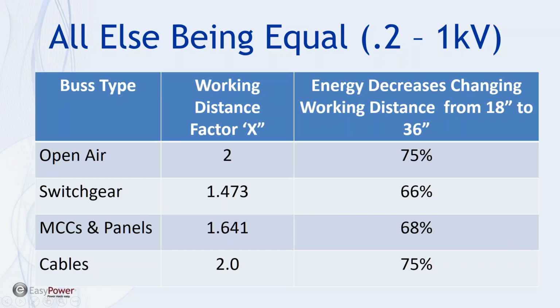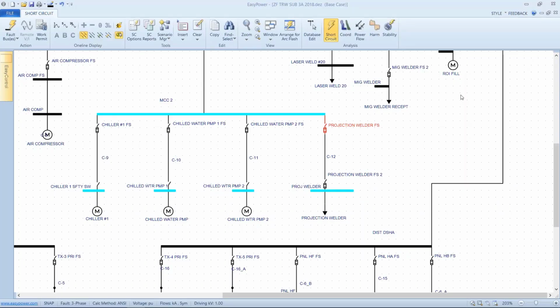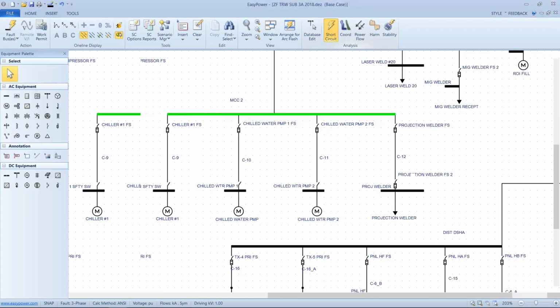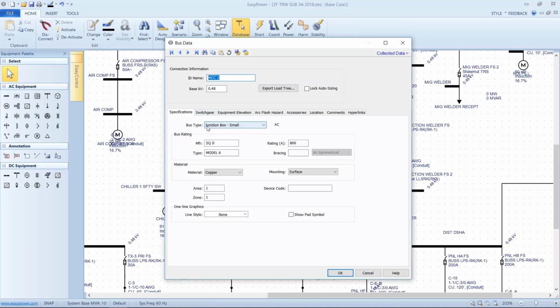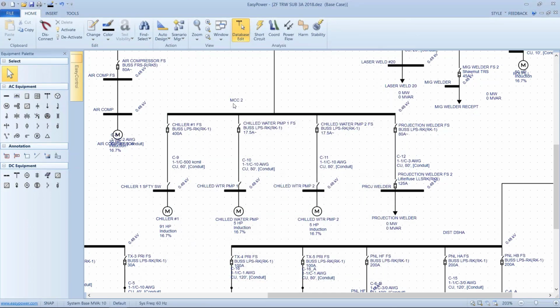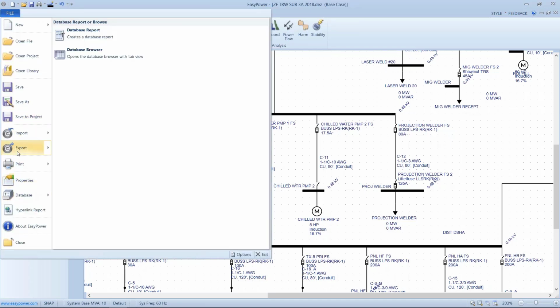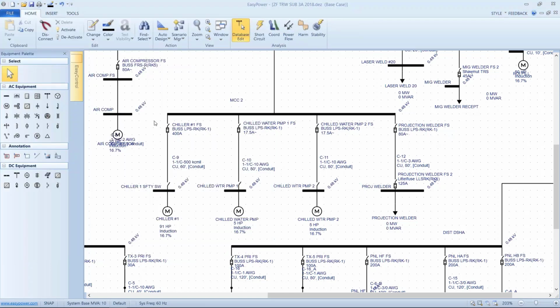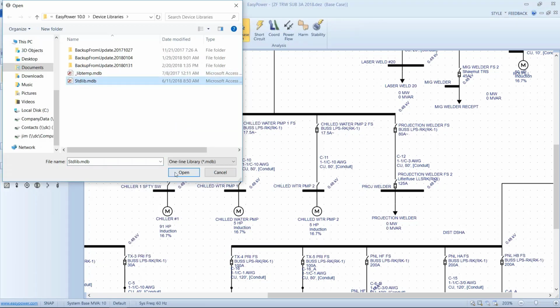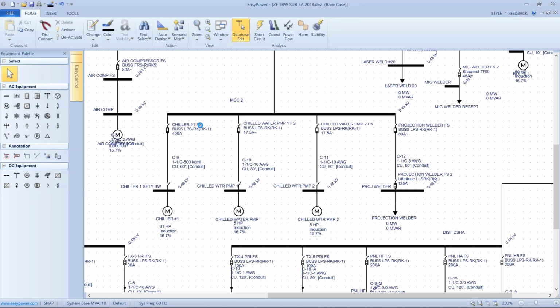Now, just to take a step back, if I look at the example we were just looking at, the person that did this modeling selected a junction box as the type of panel or type of bus that he was using, even though it was labeled motor control center. This lookup table that we're talking about is included in the device library. And so if I go out here and open the library, standard lib, and again, anyone can look this up on the tools.